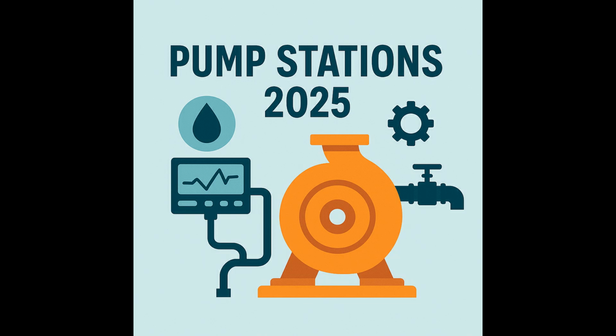Okay, that's a real light bulb moment for me. So staying in that POR green zone isn't just about saving a little bit of energy. It's fundamentally about protecting the pump from being literally eaten away by cavitation. Exactly. By keeping that NPSH margin healthy, it underpins both reliability and efficiency. Absolutely. So to quickly summarize for you, POR means optimal efficiency and reliability, the green zone. AOR is acceptable but less efficient, higher risks, the yellow zone. Cavitation is that destructive vapor bubble collapse inside the pump, and a healthy NPSH margin is critical. When flow shifts outside the POR, especially too high, that margin often shrinks, making cavitation far more likely.